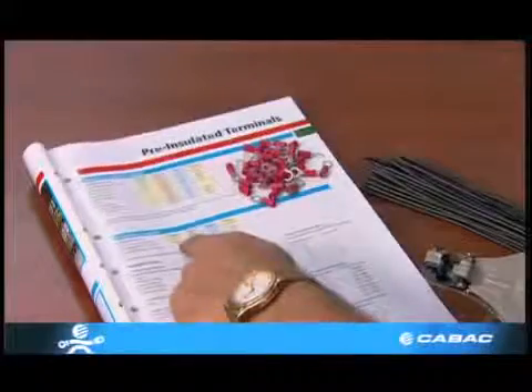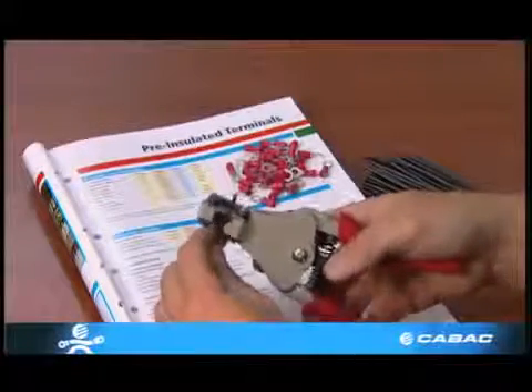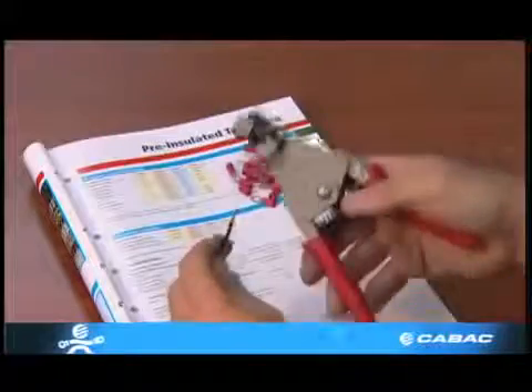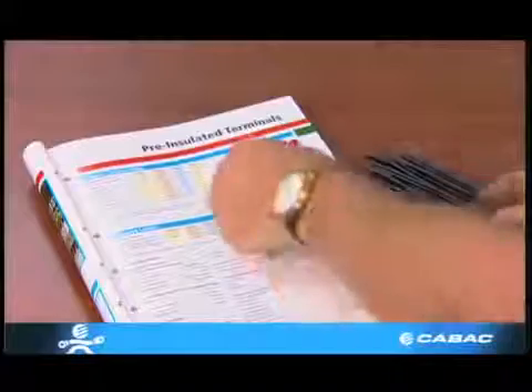It's important to get the strip lengths right. The CABAC catalogue is able to provide the correct strip lengths for all conductors. However, in general, the wire should protrude one millimetre out of the front end of the terminal.